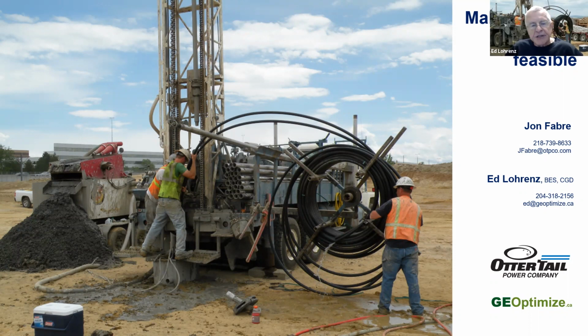In order to model that accurately, you'd really want to get a water well test in the area, and basically it's really to try and determine how much groundwater flow there could be across the borehole field, what the depth of the fracture zone is. For example, in a limestone aquifer, is the fracture zone maybe 10 feet deep, or is it 100 feet? And that would have an influence. If you're near the ocean, you might have some influence from tides going in and out and things like that. But there's no easy software that I know of where you could inexpensively model that. There are hydrogeologists that use something like FeFlow that will do that, but it's a pretty expensive process.